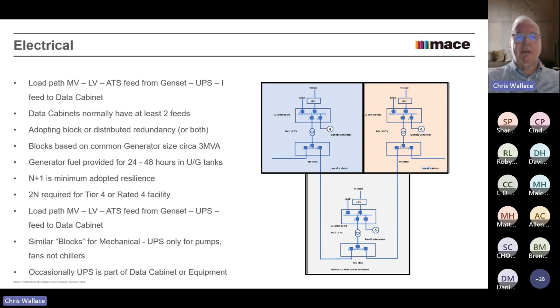So basically it's just the load path from the MV through the LV, or from the ATS if the power's off, to the UPS, to the data cabinet. And a similar block might be for mechanical without any UPS. It might be only a UPS for the pumps and the fans, but not the chillers. And occasionally we see some customers who don't really want a big centralized UPS. What they'll do is say, right, all my servers will have their own inbuilt UPS. So their server will be almost like a laptop, with its own little battery pack.